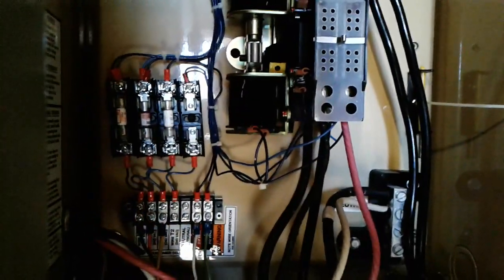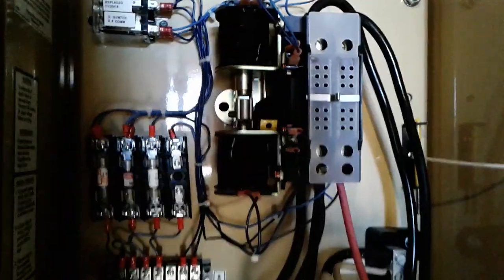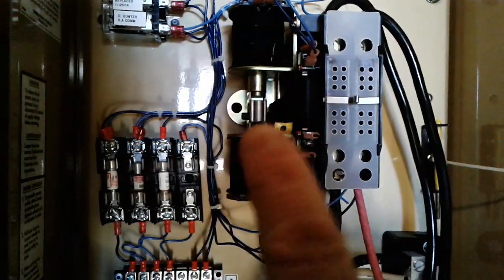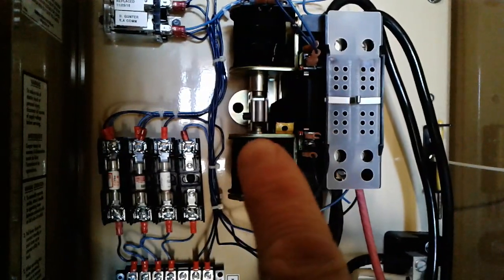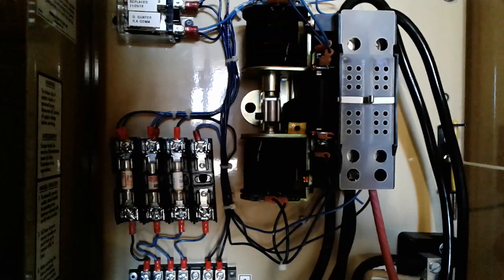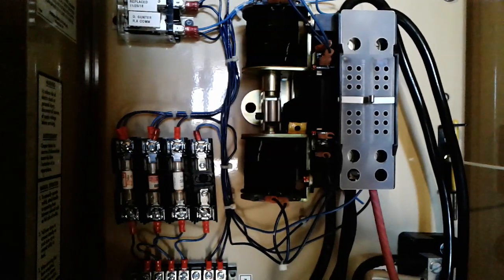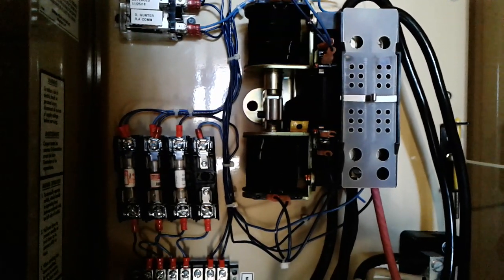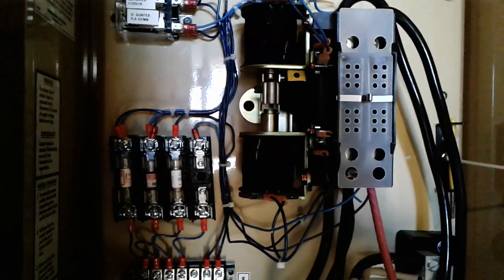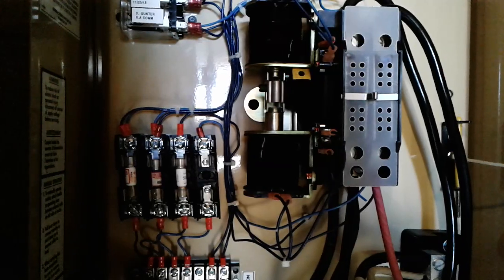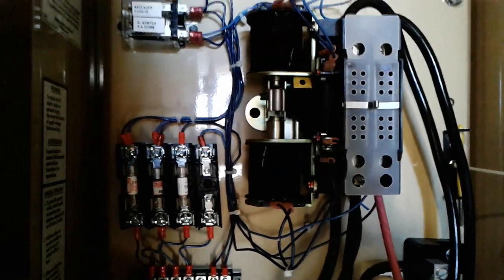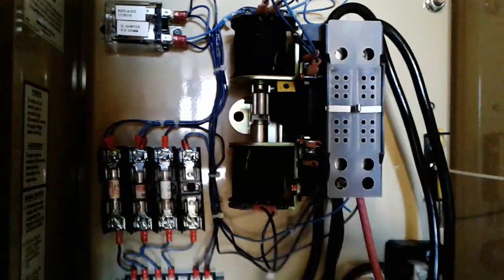And now we will restore the mains, and with another time delay, the generator should sense we're back on mains, and this transfer switch should throw again. Generator will continue to run for a minute. So there we go.